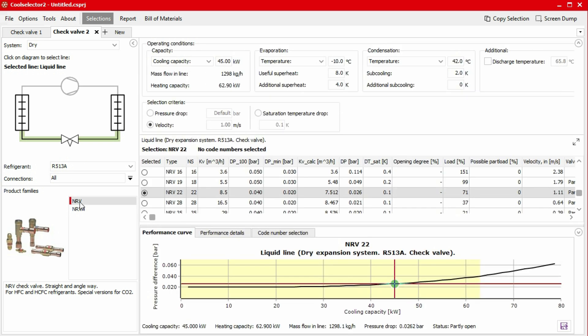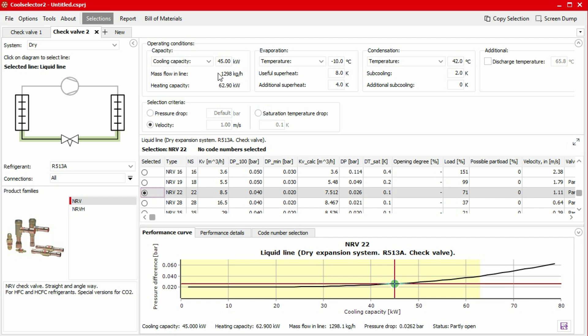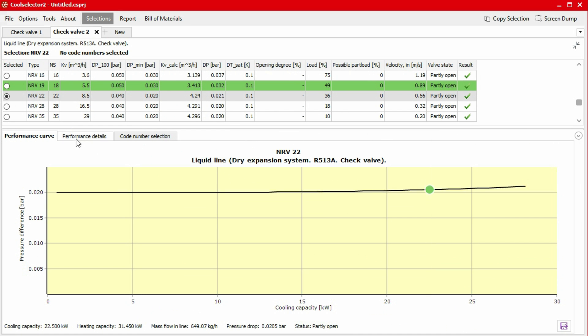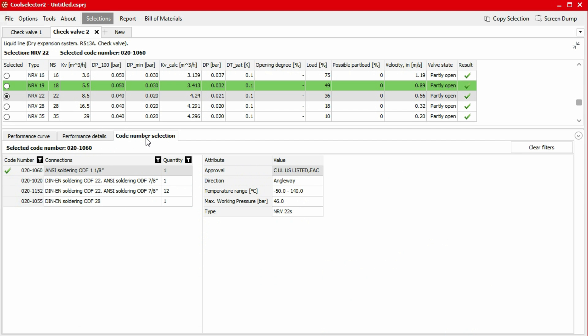Additionally, because there are little to no vibrations, a partially open condition is possible — this is down to the minimum pressure drop. We can see that the suggested product is the NRV 22 valve. The pressure drop across the valve is 0.026 bar at full load, and the minimum pressure drop for the valve to operate is 0.02 bar. If the valve operates below this, the valve will become unstable. To check the part load condition, we can halve the capacity from 45 kilowatts to 22.5 kilowatts. We see that NRV 22 has a pressure drop of 0.021 bar, which is above the minimum pressure drop and indicates stable operation. When the pressure drop is near or equal to the minimum pressure drop, another model should be considered. Additionally, the saturation temperature drop is low at 0.1 kelvin — this is important because a high pressure or temperature drop could lead to refrigerant flashing to a gas phase in the liquid line. In the code number selection tab, we can find the product's code numbers for different connection types.